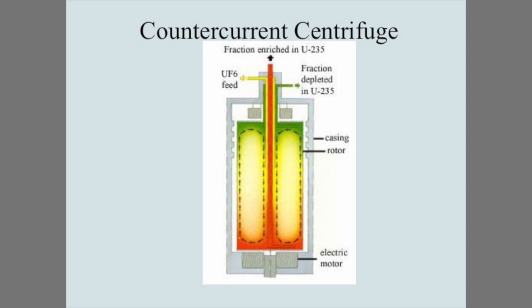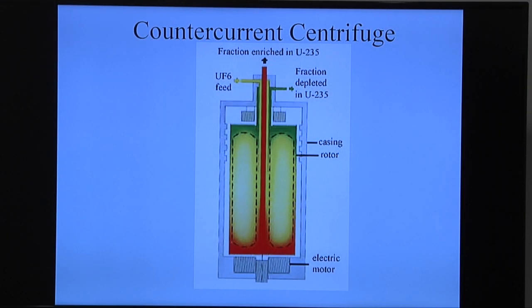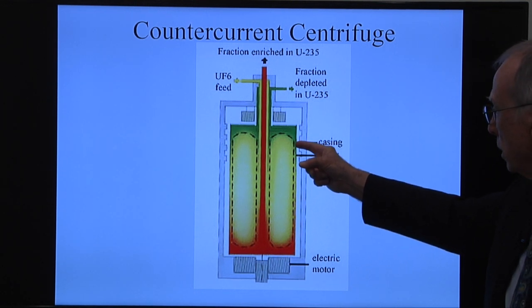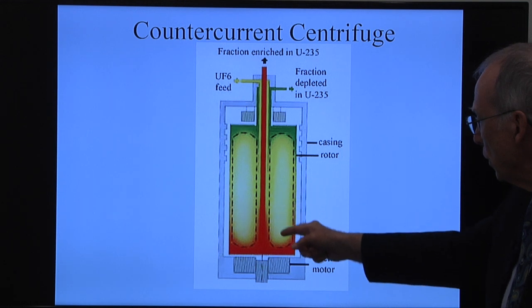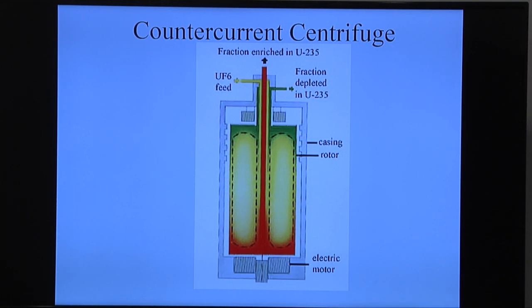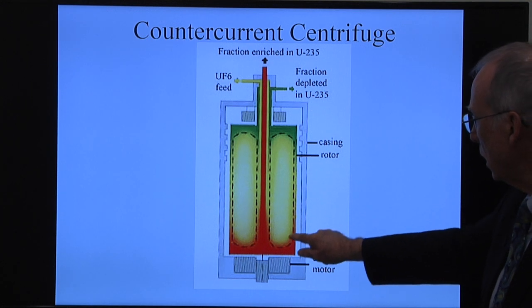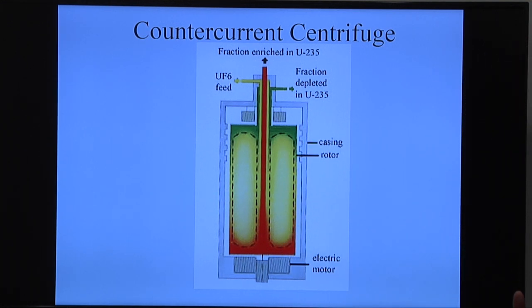That centrifugal separation is then amplified, or compounded, by having a countercurrent flow. In my diagram, you can see the arrows going up and down, so we have a flow in that regard. You can make it go either way depending on how you control the temperature on the rotor wall, so it could go clockwise or counterclockwise. That's something you decide when you build your centrifuge.